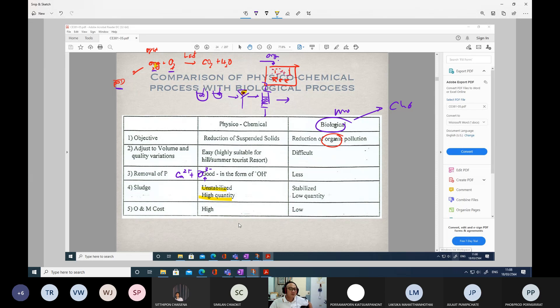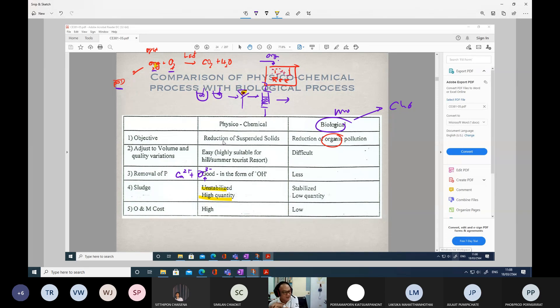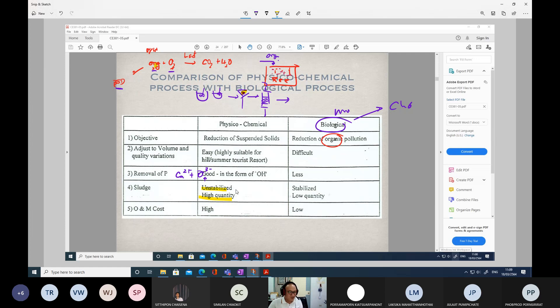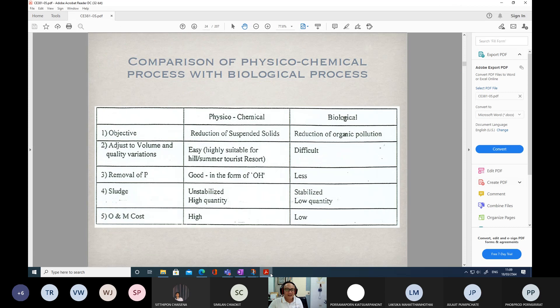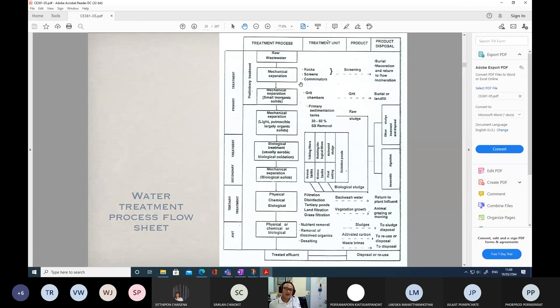For operations and maintenance cost, the biological process is very cheap — you don't need to add any extra chemicals except just providing oxygen. But for the physical-chemical process, we really need to add chemicals continuously. A large amount of chemicals must be added in daily production — we have to spend money on alums and other coagulants to reduce the colloidal and fine particles.